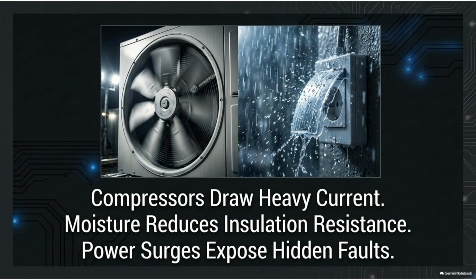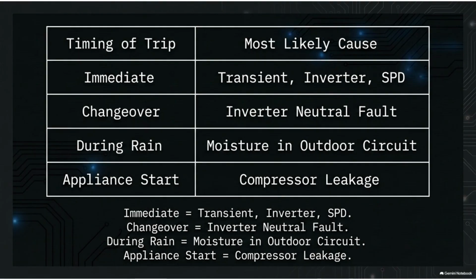Appliances with large compressors draw heavy starting currents. Additionally, moisture in outdoor circuits reduces insulation resistance. Power surges can expose these hidden faults, causing the RCCB to trip. The timing of a trip can help identify the cause. An immediate trip often points to transients or faulty equipment, while issues during rain or appliance startup suggest specific insulation or leakage problems.